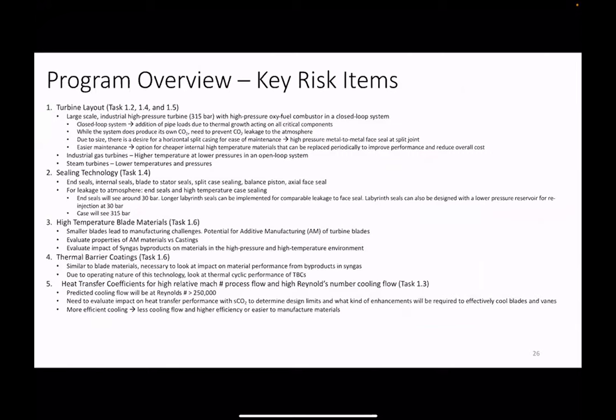Sealing technologies — we want to evaluate the right end seals and internal seals. This includes blade-to-stator seals, tip seals on the blades, end seals (which we're going with labyrinth seals), and balanced piston seals. Are we going to use axial face seals? So we evaluate what's going to work in the system.